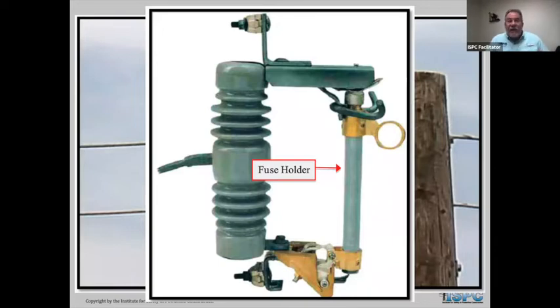So what you saw in that video was one fuse holder went out, and we started single phasing the customers off of the 3 transformers, and then the other 2 fuses blew. Did it make it safe? Well, if the energized line came back on and there was nothing to show any fault current back to the recloser, it would not have tripped again.